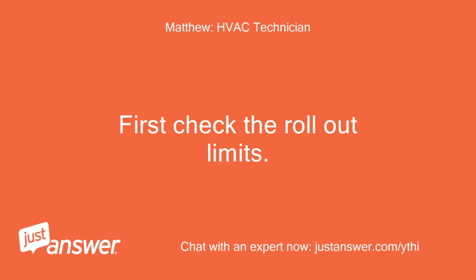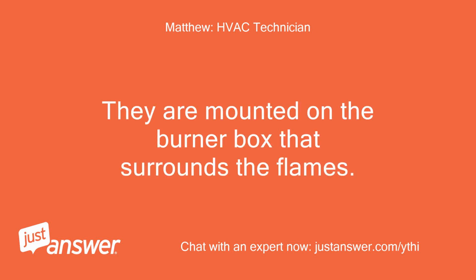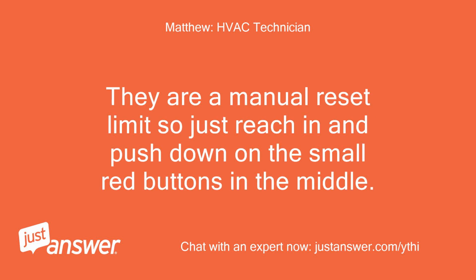First, check the rollout limits. They are mounted on the burner box that surrounds the flames. They are a manual reset limit, so just reach in and push down on the small red buttons in the middle. If they are open, then this button will click down.